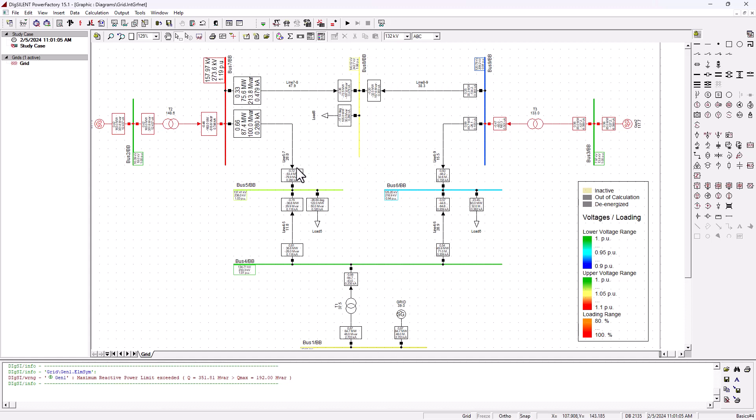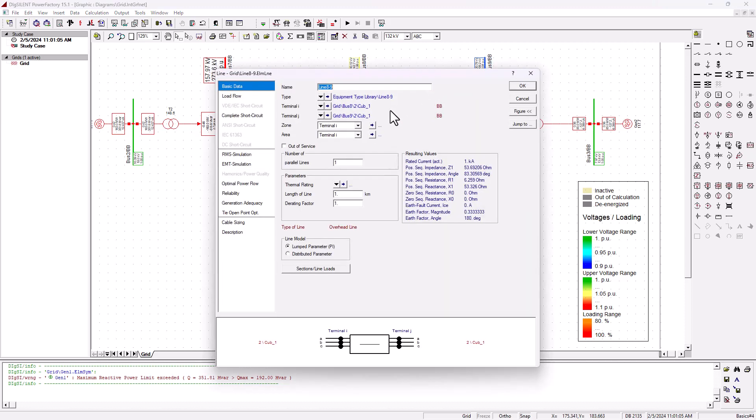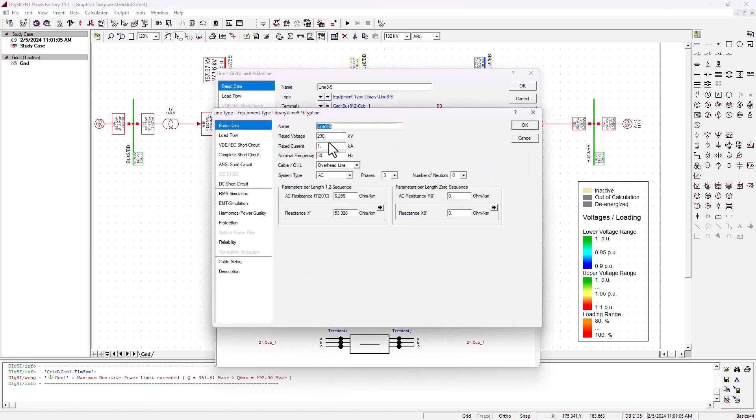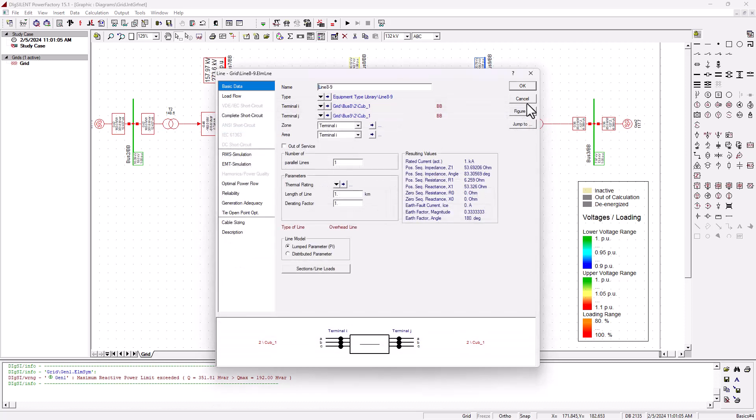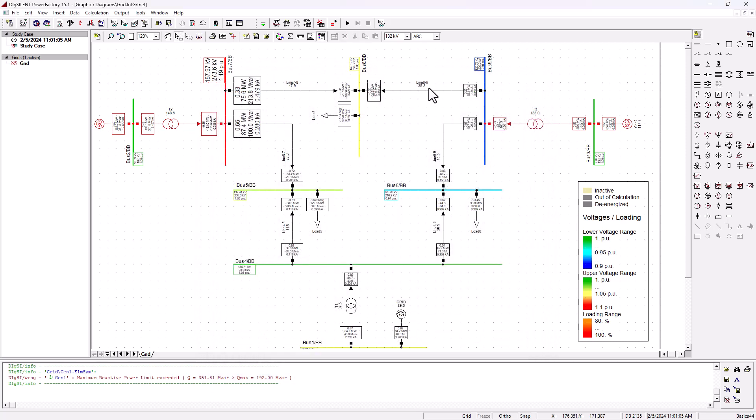This is why it is overloaded. And that's a problem that must also be addressed. Elsewhere on the network, we've got greens and blue. That is acceptable. And our lines are not overloaded because remember, we spec all our lines for one kilo amps.